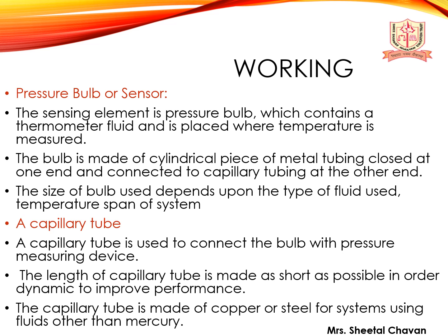The capillary tube. A capillary tube is used to connect the bulb with the pressure measuring device. The length of the capillary tube is made as short as possible in order to improve the dynamic performance. The capillary tube is made up of copper or steel for a system using fluid other than mercury.